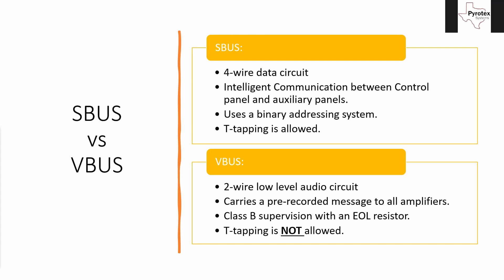The VBUS is a low-level audio circuit — it doesn't have enough power to drive speakers itself. Even if you only have one speaker circuit on a job, you can't skip amplifiers and power it off the VBUS; there's not enough power for that. It just feeds amplifiers, and the amplifiers make the signal strong enough. The SBUS, on the other hand, because of its intelligent communication and addressing, allows T-tapping because the panel will know if any device drops out — it's monitoring individual communication, not waiting for an end-of-line resistor.